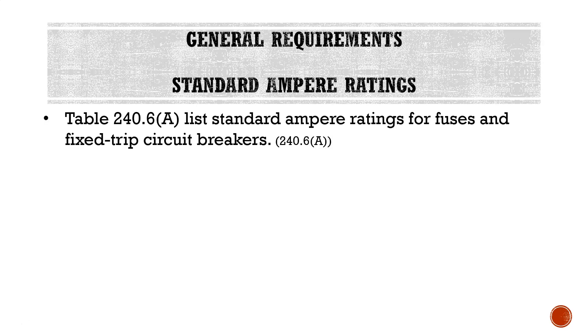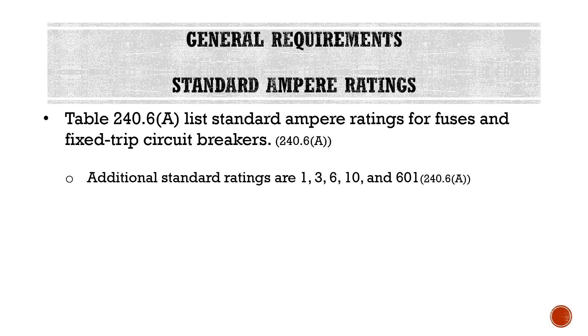Moving on to standard ampere ratings: Table 240.6A lists standard ampere ratings for fuses and fixed-trip circuit breakers. This table is one we'll be going back to repeatedly, similar to Table 310.15 B16. Table 240.6A essentially tells us what size overcurrent protective device we're going to be using for a circuit. In addition to the ratings listed in Table 240.6A, there are additional standard ratings of 1, 3, 6, 10, and 601 for fuses only — these sizes do not apply to circuit breakers.